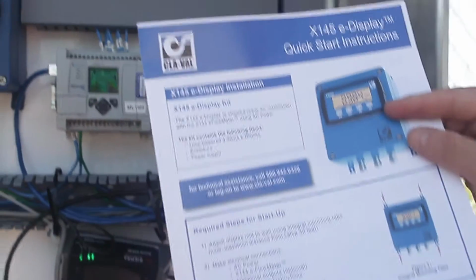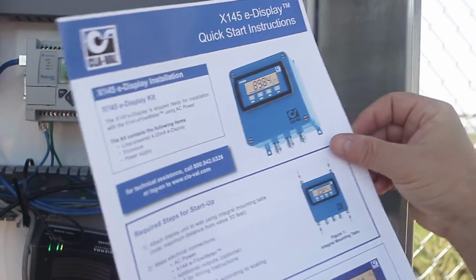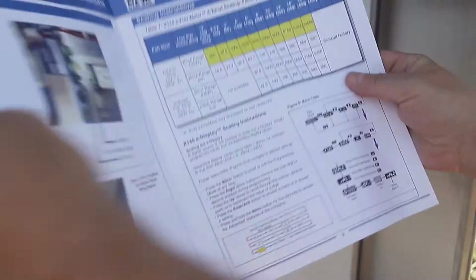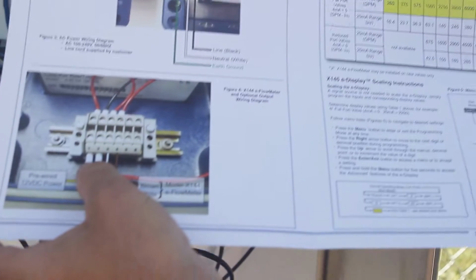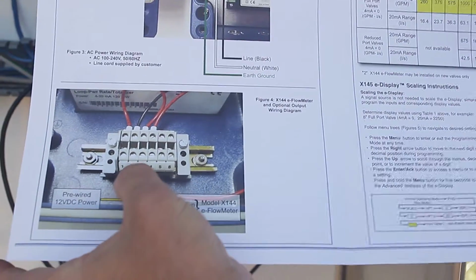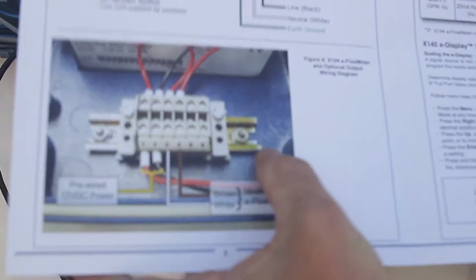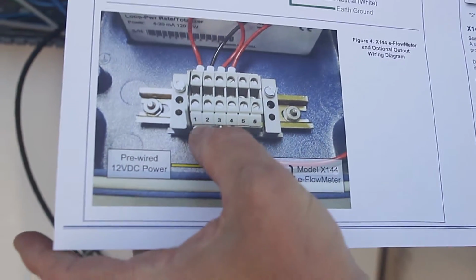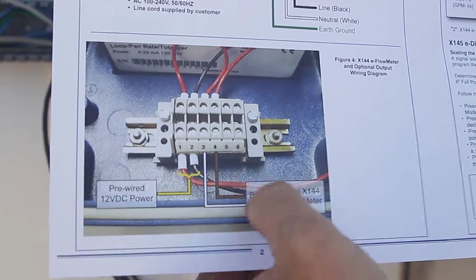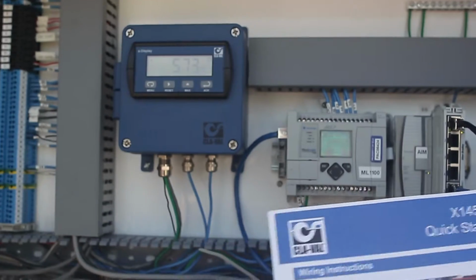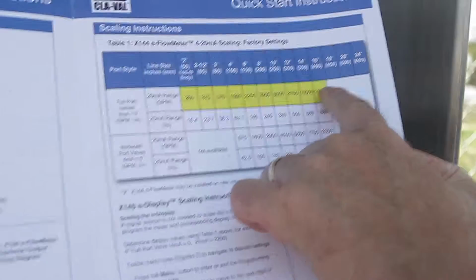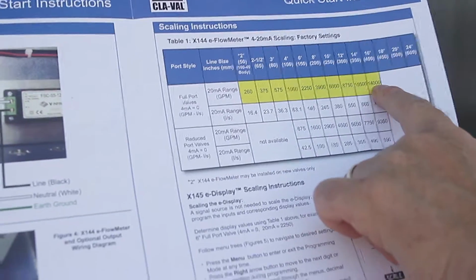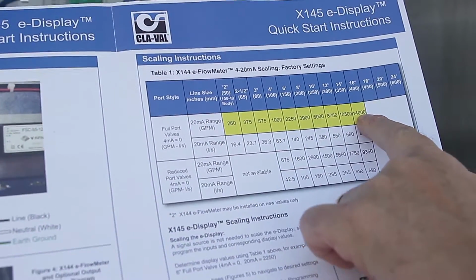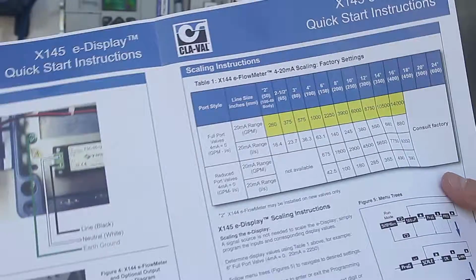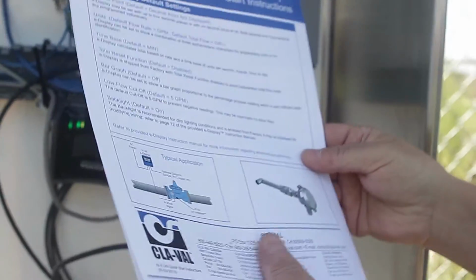This is on the display itself, showing the setup wiring for the display, which they have already finished, showing some of the wiring internally here. They brought the 24 volts to terminal 1 and 2 and bypassed our AC power supply. This is a DC system anyway, which then powers the flow meter on the valve, which then goes into the panel meter right here. Now a 16-inch valve here is in the chart right in the same literature. Full scale on a 16-inch is 14,000 GPM, but we rescaled that for MGD. So that's already finished, and it's very simple setup.